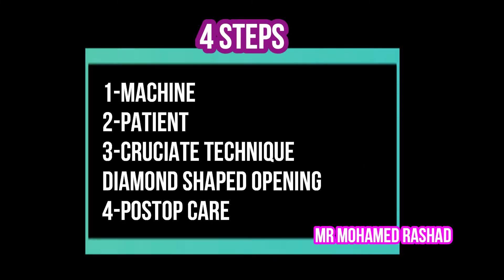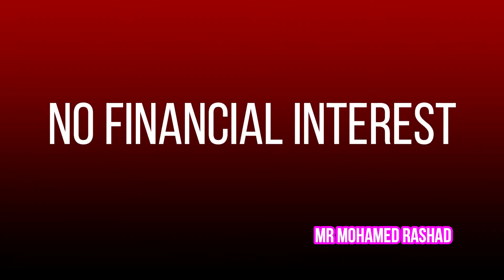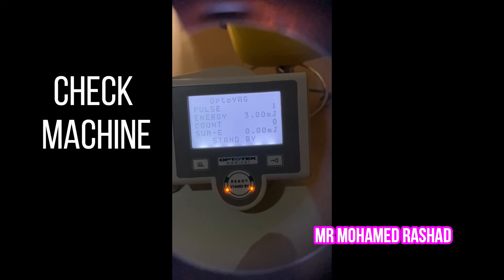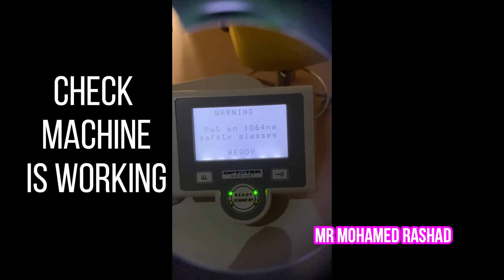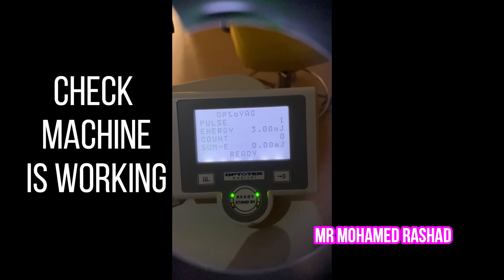There are four steps: you have to know the machine, prepare the patient and the eye, do a cruciate technique, and manage post-operative care. For the machine, the most important thing is to put it on YAG mode, do the settings, and sometimes we need a contact lens. You have to make sure you are not on SLT mode, and that the machine is working well.